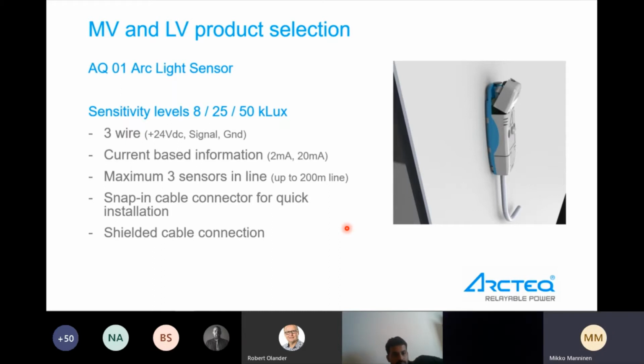AQ01 arc light sensor. We have 3 sensitivity levels, and this first one, this 8000 lux, we can say is 99% of all sensors delivered. So that has been fine-tuned to the spectrum level of the real arc many years back, and has been like that from the beginning.